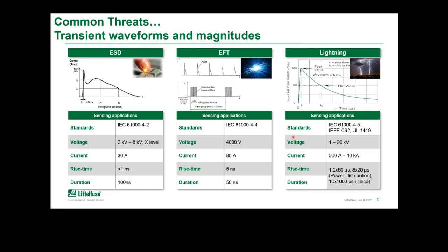And then for lightning events, there's a few different standards. Globally, the typical standard that is referenced is 61000-4-5. In North America, there's some other standards that are referenced, typically IEEE C62 or UL 1449. Now, the test waveform that's typically used, especially if we're talking power circuits, is what's called a combination waveform. And the combination waveform consists of an open circuit voltage waveform, which has a 1.2 microsecond rise time to a 50 microsecond fall to half peak. And then it has a short circuit current waveform that consists of an 8 microsecond rise time and a 20 microsecond fall to half peak.